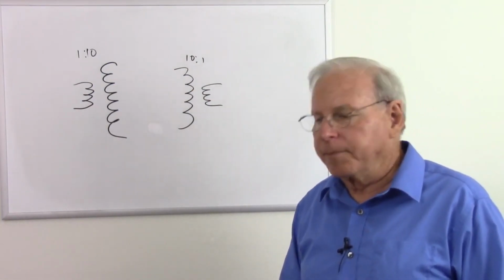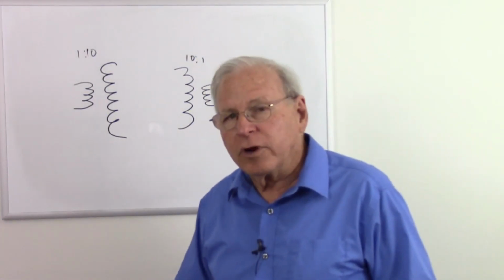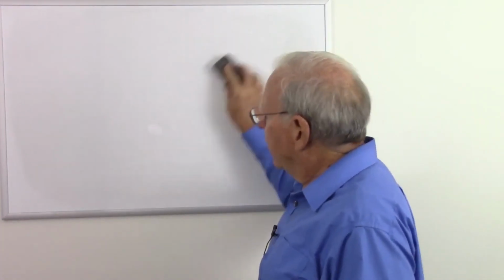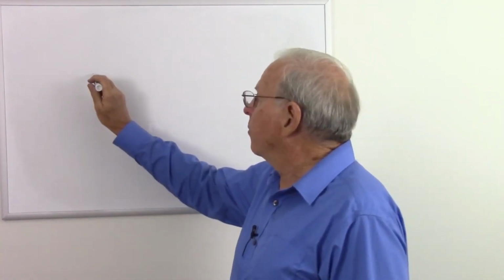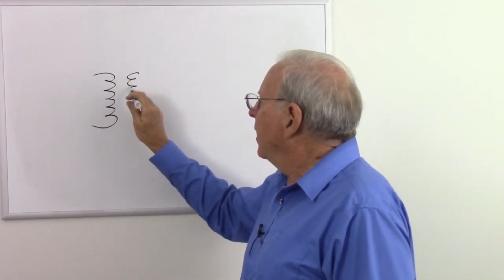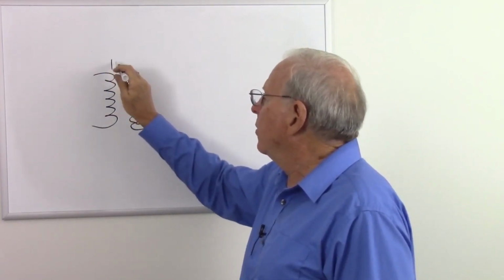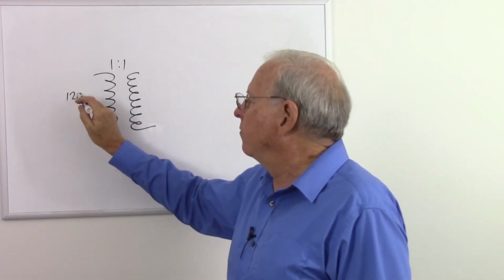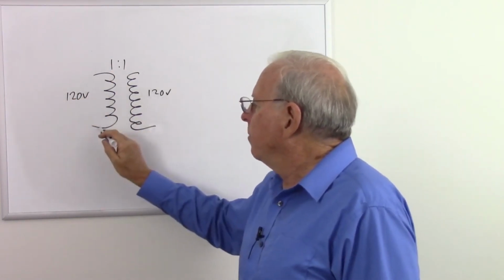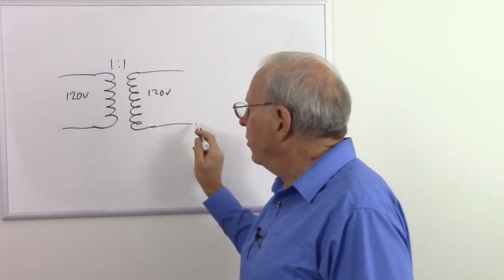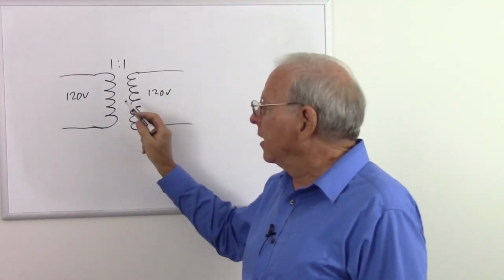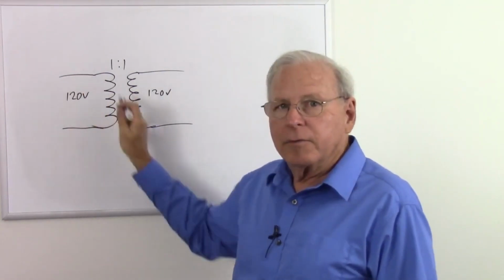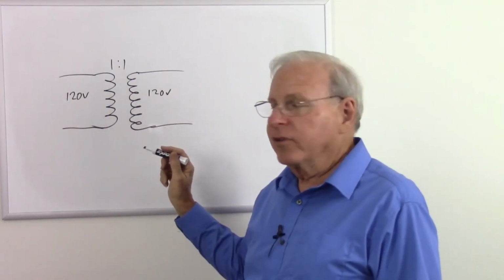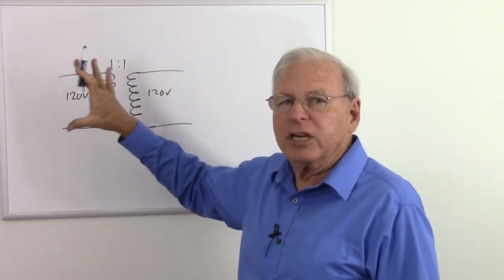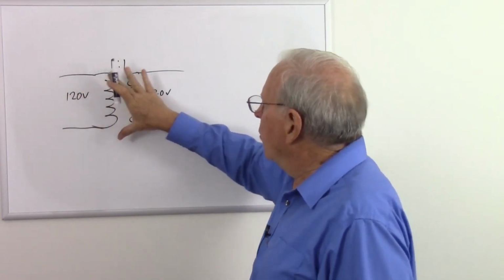That's the ones we think of most often. But another type of transformer is for DC isolation. As I mentioned earlier, direct current doesn't go through a transformer. So let's make these coils the same. Now, an isolation transformer doesn't have to be a 1-to-1 ratio, but basically 120 volts in equals 120 volts out, and usually isolation transformers are 1-to-1. The purpose of them is primarily that a DC component on one side won't transfer to the other — if I have some DC offset or DC noise, it won't transfer across. So it isolates one side from the other.